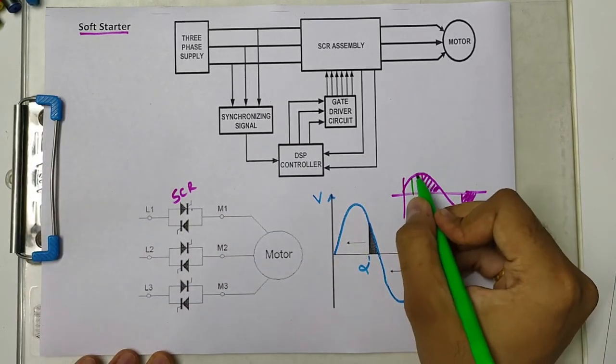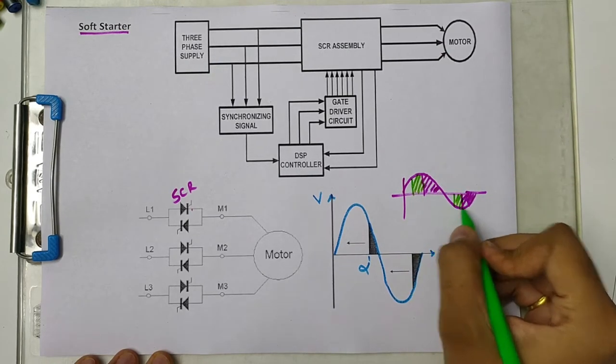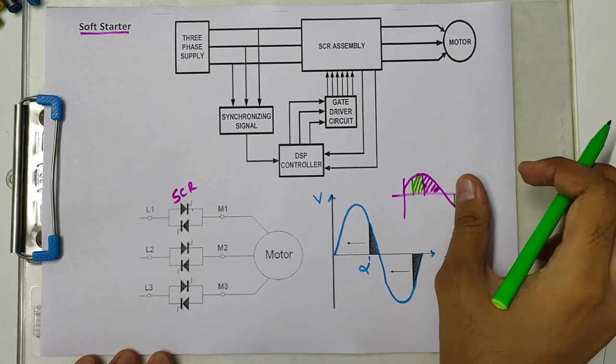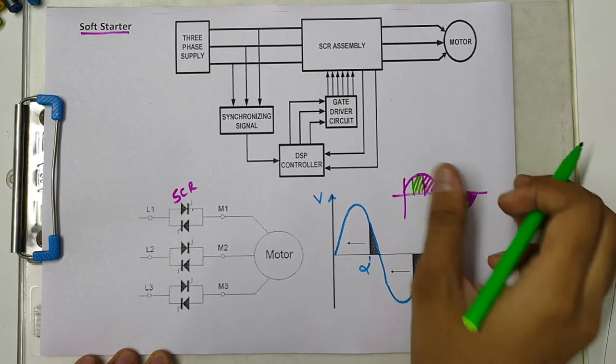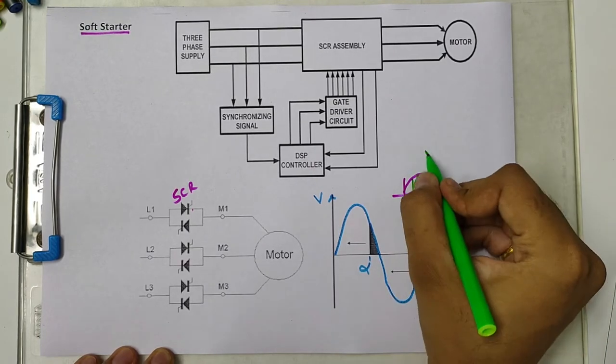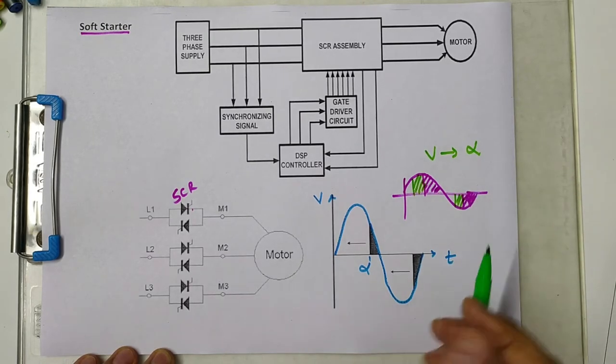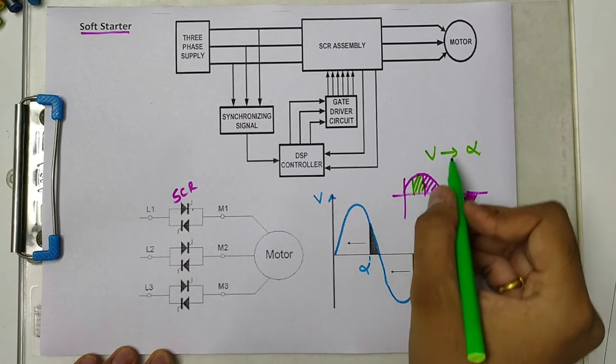If we further increase the value of alpha, the thyristor will stop conducting at an earlier point. The overall average value or RMS value of the voltage supplied to the motor depends on alpha. As we increase or decrease the firing angle, the voltage value will also change accordingly.